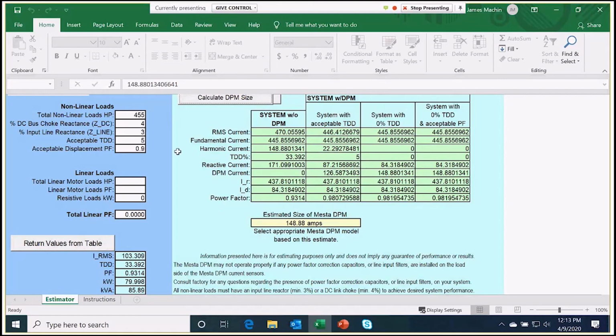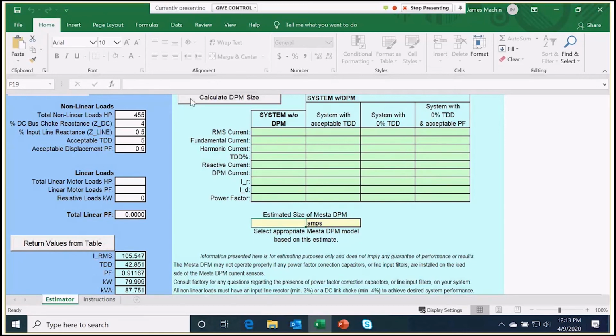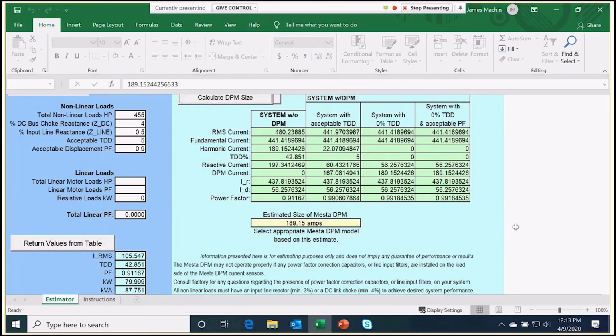through a VFD lookup table we have here, with 455 horsepower using 3% line reactors, you have 149 amps of correction required. So we'd say, okay, you need a 150 amp filter. And then you say, Jim, actually I don't have room for the line reactors here, so I'm going to take them out, and I can get a new number, and I have 190 amps of correction. So now you have a 200 amp filter.